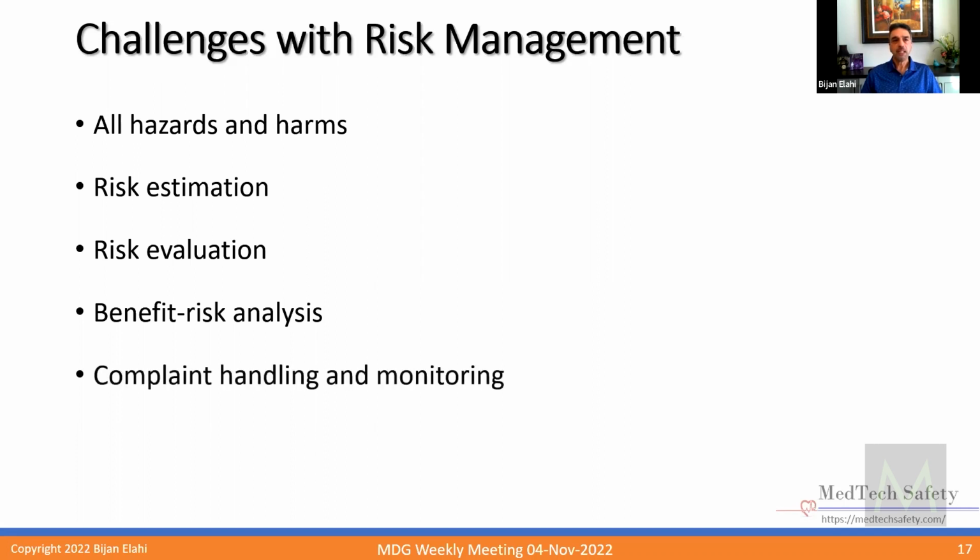Complaint handling and monitoring is another challenge. If anybody has worked in complaint handling, you see that complaints are a hodgepodge of information, incomplete, unclear. You can't tell whether there's even causation. A patient may have multiple comorbidities. There could be multiple devices working on the patient, and the patient gets harmed. You get a call. You can't even tell if it was your device that did it. You don't know if there was another disease that did it. You don't know whether somebody tampered with a medical device. You don't know if they followed instructions or not. It's difficult. And that's the complaint handling part.